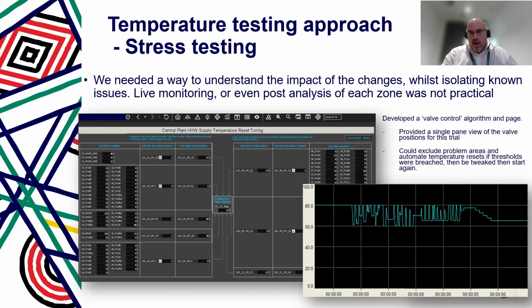And so you'll see in the bottom corner there, that's the temperature profile when we started testing. So we'd turn it on, and we'd find certain areas that were problematic. We'd make some slight changes, and it would sort of fluctuate up and down. And once we got a handle on what was happening, you'll see at the end there, we were able to refine those changes and step down through those temperature set points and maintain that lower temperature set point.